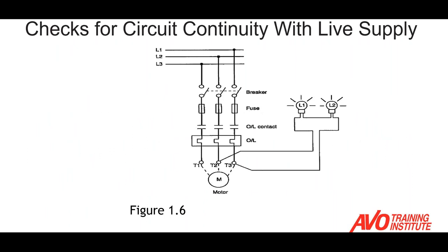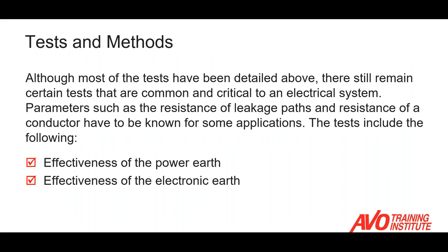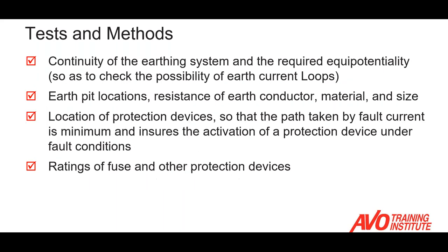We can also use two lamps with a power supply to check between phases — we should have a continuous path and get illumination on the circuit. Our probes and tools need to be insulated to minimize exposure to live conducting parts, and to minimize the inadvertent bridging of two terminals at different potentials, which can cause a short circuit and expose the technician. Most of the tests we've detailed are looking for resistance leakage path and resistance of a conductor for the known application — we're looking for a path to ground, and that's what we're trying to avoid.